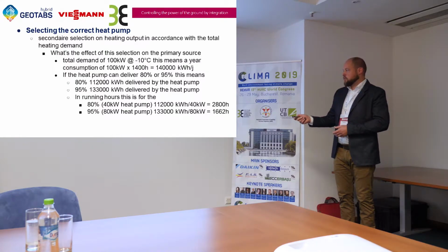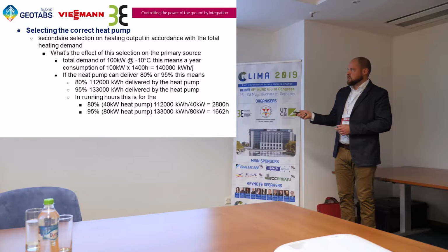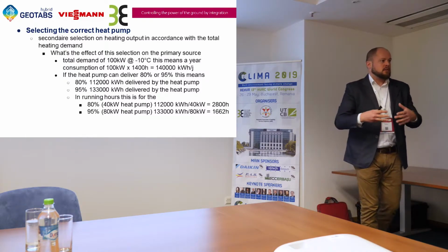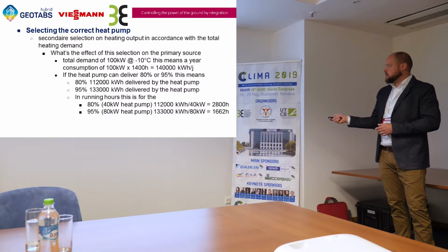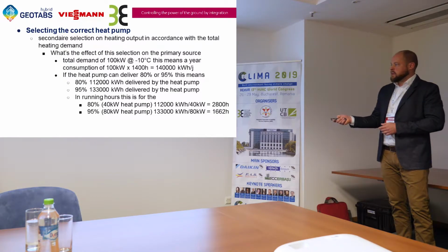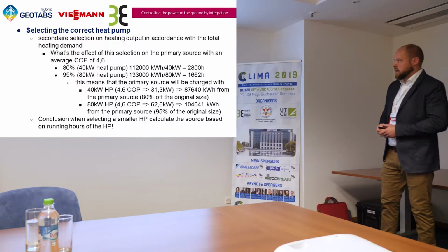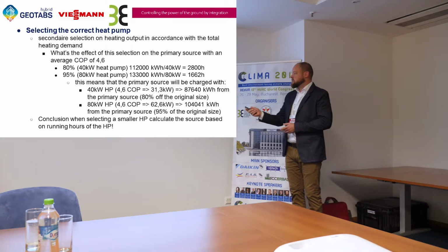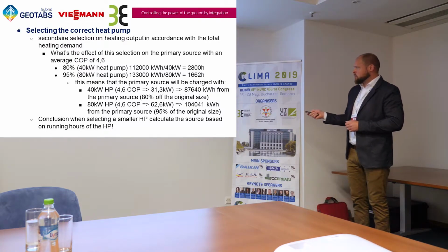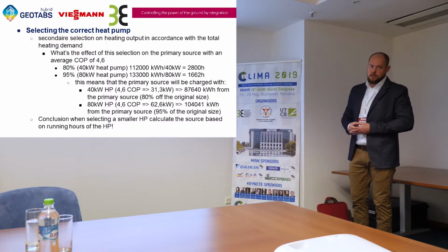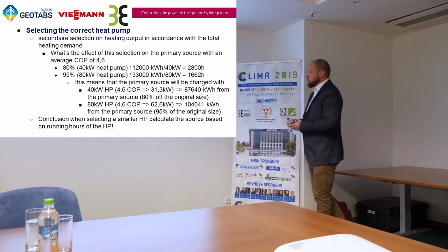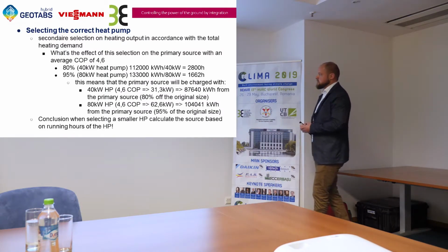So this means that the heat pump, the small heat pump of 40 kilowatts, will actually run 2,800 hours. That's double the normal calculated running hours. So 1,400 hours in full power means at 40 kilowatts that we will run 2,800 hours per year on this heat pump. When we have the heat pump of 80 kilowatts, we will have 1,662 running hours. What does that mean on the source? So I first went with the normal conditions, the normal condition of a COP of 4.6 in this example, because you saw it in the table at the beginning. So that means with these running hours for the two heat pumps, 40 kilowatt heat pump on the secondary side with a COP of 4.6 will use 31 kilowatts on the evaporator side. So that means that when the running hours are 2,800, we will deplete the source with 87,000 kilowatt hours.